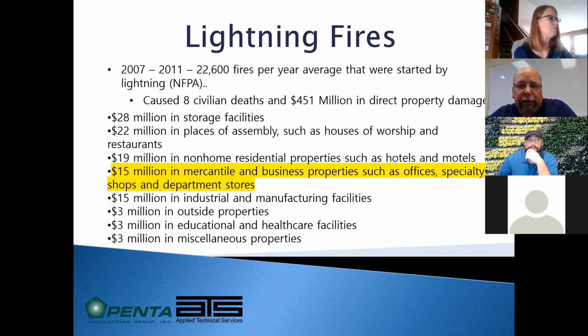There are some alternative systems we'll show you in a little bit called early streamer emission, and they claim they would generate the leader and more or less cause lightning to strike that particular air terminal and pull it to ground. Some of them were even charged with radioactive sources. In the end, the United States does not recognize that they provide any better protection, and there have been numerous cases where their claims have been debunked. But the leaders are basically the points of the energy differences, and in the lightning protection system those are generally the air terminals. By placing them where we're placing them, those are going to be the points where those leaders would generate. I hope that answers the question?